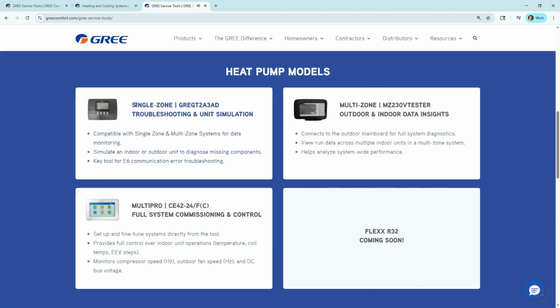Now, what I wanted to tell you guys is on the single zone service tool versus the multi-zone service tool for the mini split line, MultiPRO has its own specific service tool. But on the mini splits, we have a single zone and we have a multi-zone. And we talk about this in the video. But just so you know, the multi-zone service tester, when you hook that up to the outdoor unit, there's a plug-in on the board you plug it up to, and you can run full diagnostics and analyzation on that machine of the outdoor unit and all of the indoor unit run data. You toggle through whichever indoor unit you want to look at. Say you've got 4 indoor units, you can toggle through the parameters of each indoor unit through that multi-zone service tool, which is a pretty neat tool.